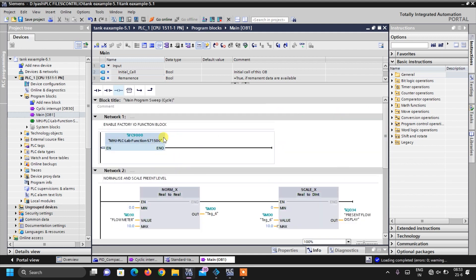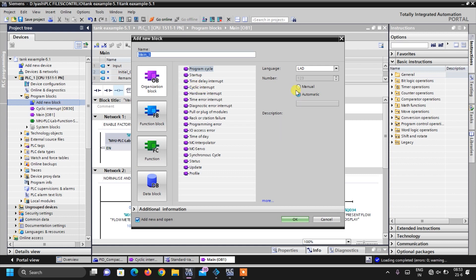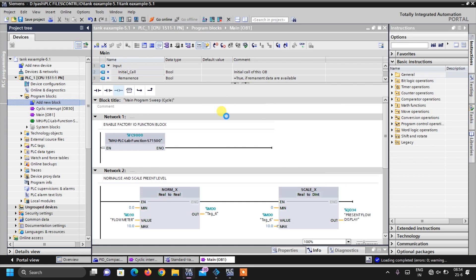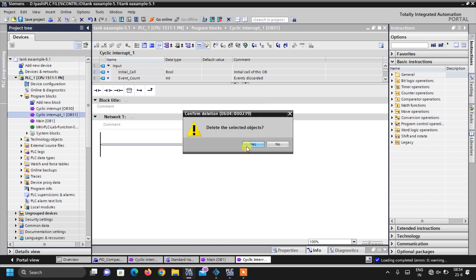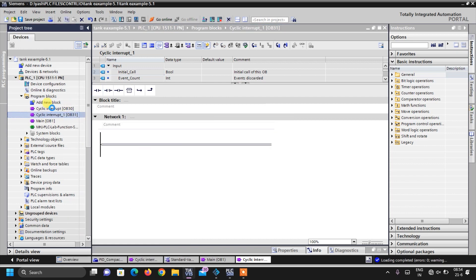Now quickly coming to the cyclic interrupt: double-click on 'Add New Block'. For PID instructions we have to create a different OB. Click on 'Cyclic Interrupt', click 'Automatic', and click OK — the cyclic interrupt OB will be created. I have already created it, so I will just delete the new one and show you my existing cyclic interrupt OB30.